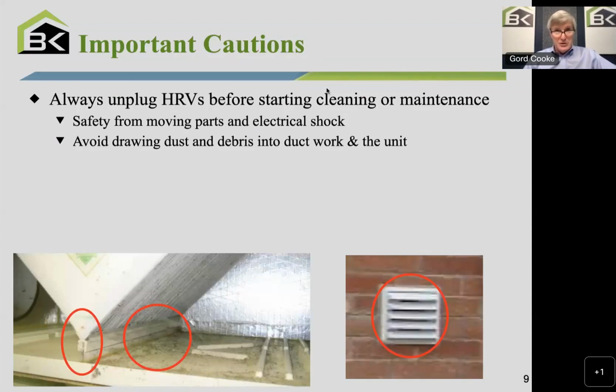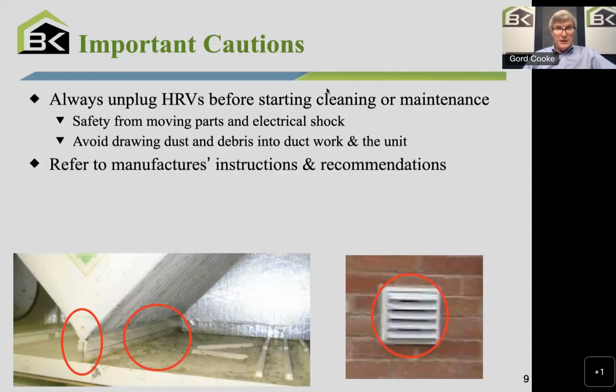And 99% of HRVs are in fact electrical plugs, so you don't have to do a disconnect. You simply unplug the unit, and you'll find that the cord on an HRV is less than 6 feet long to facilitate that. Simply unplug it. And then of course, I always refer to manufacturer's instructions and recommendations as to how to best clean. What we're going to show you here is pretty generic cleaning, but this will be good for at least 95% of the HRVs that are going to be in your communities.